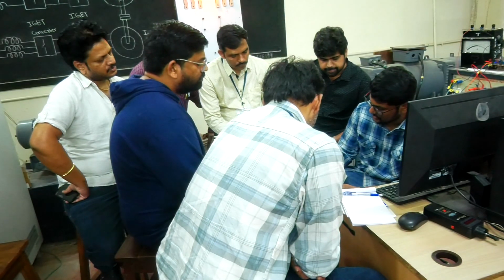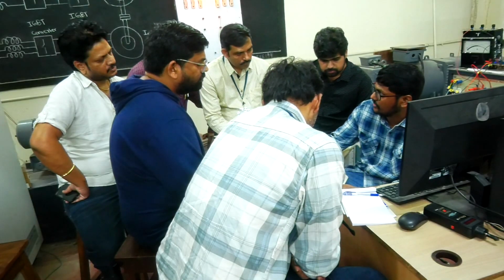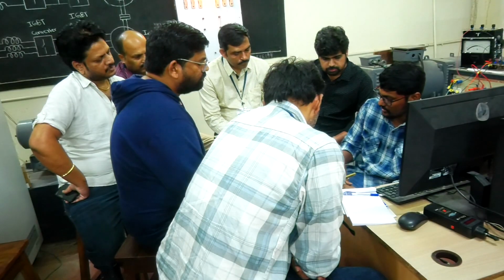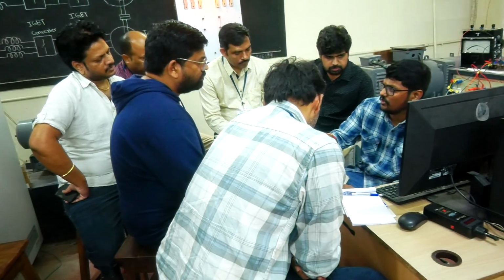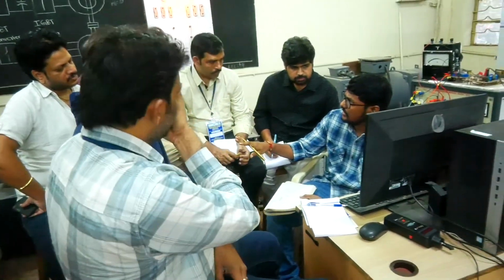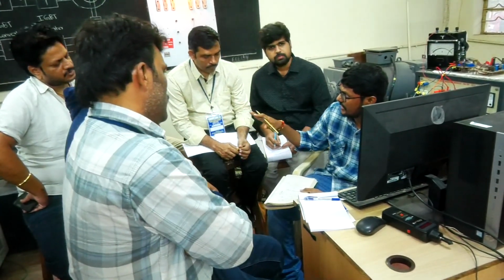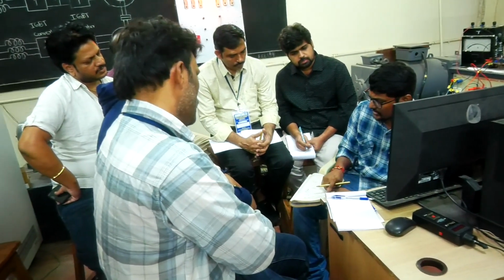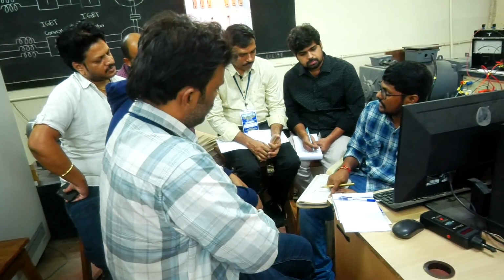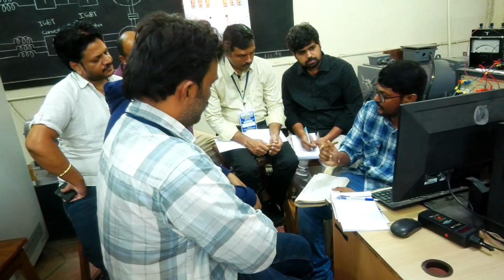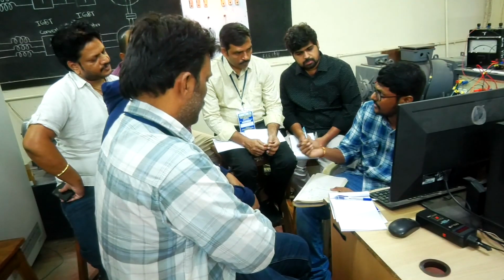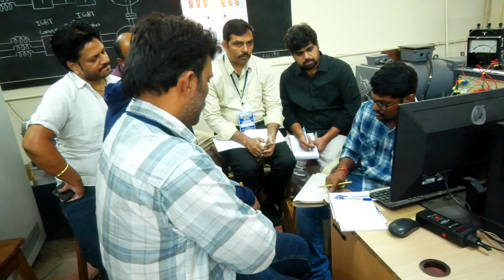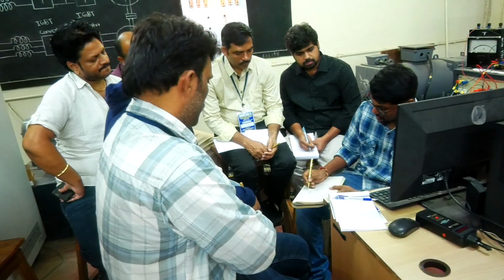After getting the 1, 0 switching states, these are directly applied onto the inverter. Then the inverter will give us the required voltages as per the closed loop. These required voltages get applied on the motor, and the motor will run at the particular speed. Depending on our Kp and Ki values, slowly the machine speed will reach the commanded speed. We can say this is the demanded speed or commanded speed, or the desired speed at which we want to run. So it will reach the desired speed. So this is the logic.